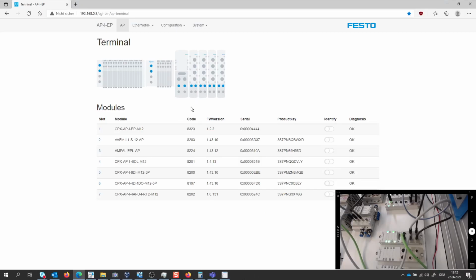One is the Festo Field Device Tool software. If this is whatever not allowed in your company to use, then use the web server. With this, you can also do this firmware upgrade. In both cases, it is of course recommended that you have no connection to the PLC, because during operation I would never do a firmware update. But as you have recognized, the Festo Field Device Tool is not caring about it, but the web server is caring about it. And it is strongly recommended that you have no process data exchange during a firmware upgrade or downgrade.